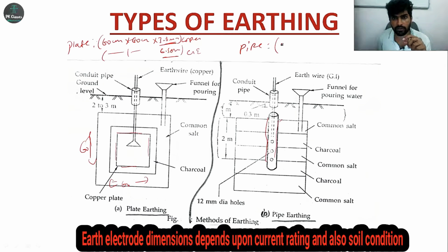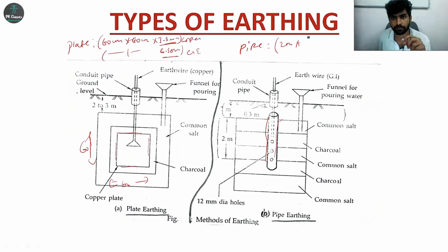Next is the pipe earthing, 2 meter long, and the diameter is 38 millimeter for copper, and 2 meter long, and 55 millimeter for galvanized iron. So these dimensions will vary based on the load and then based on the current requirement, right?